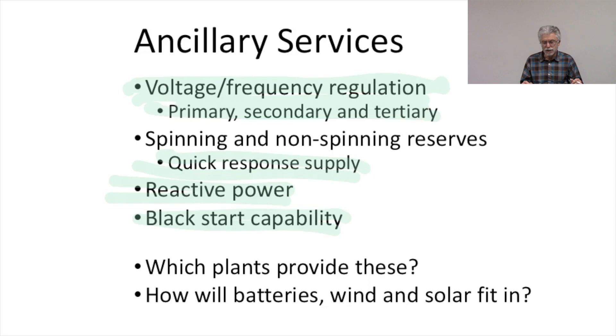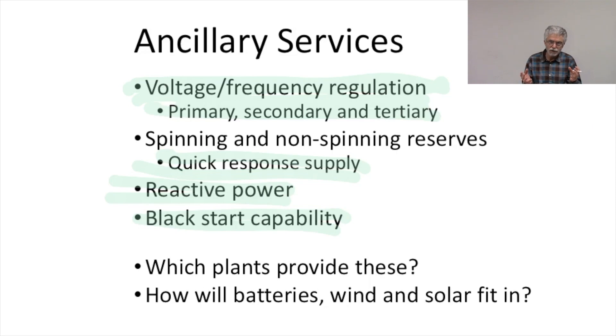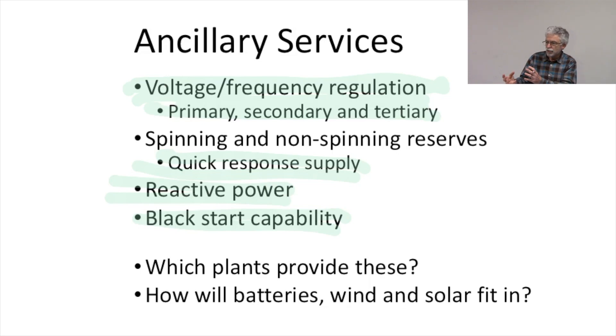This is an interesting new frontier in the case of renewable assets. We are not used to thinking about renewable assets as having particularly good black start capabilities, but that is all changing now with the advent of batteries linked up with renewable supply. This is an area where making sure we provide adequate compensation will ensure we develop the best new portfolio of renewable assets, some of which can help us provide this ancillary service.